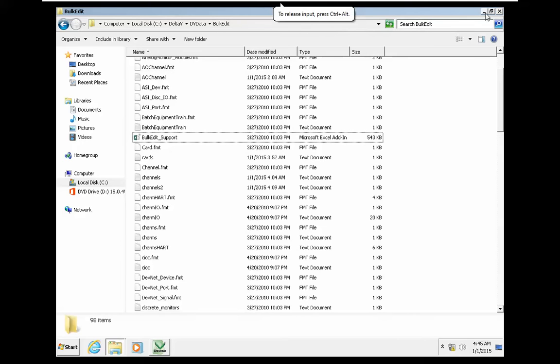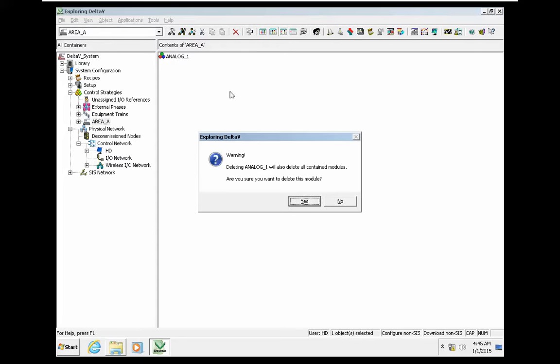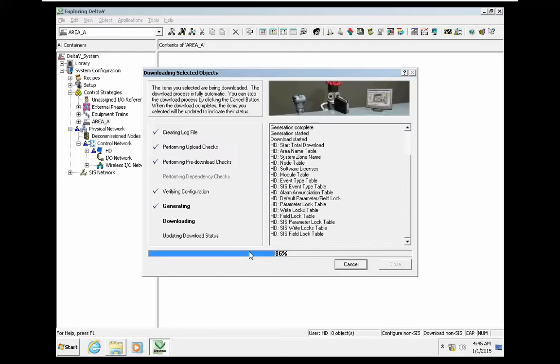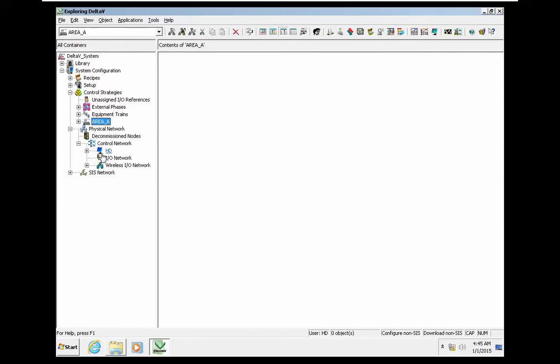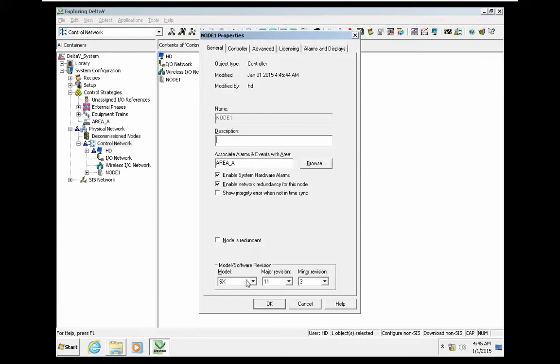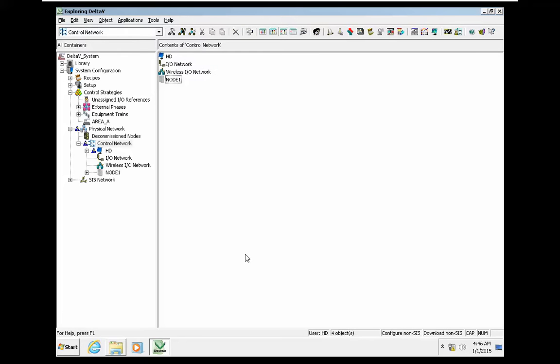I made a copy of this folder onto the desktop and I will perform a step-by-step demo: first adding the controller, then modules, and finally some programming. The first step is adding the controller — the name will be 'node1'. In the properties, we change the type from SX controller to MD controller, and the MD is the redundant controller.